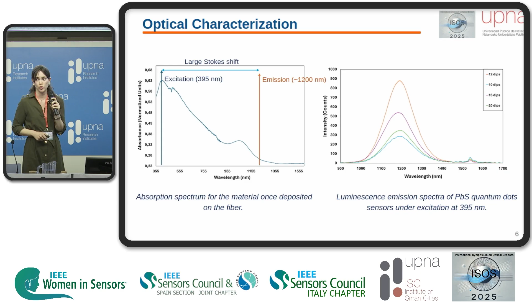For the temperature calibrations, we use a thermostatic bath with a double-walled metal cell where water circulates around the sample, and the sensor was inserted through the top. We excite the quantum dots with a 395 nanometers LED, and we collect the emission with a bifurcated optical fiber connected to the NIRQuest spectrometer. And we also use a temperature probe to control the temperature in the metal cell. The spectra were collected at each step of temperature.